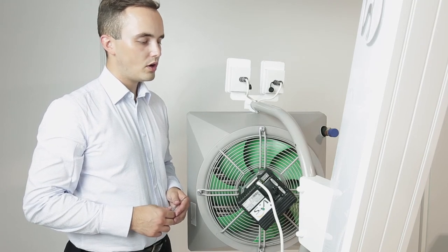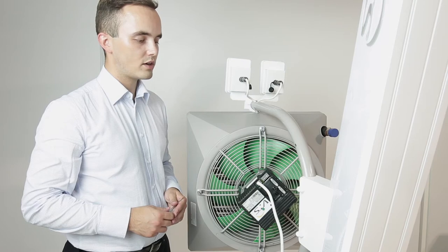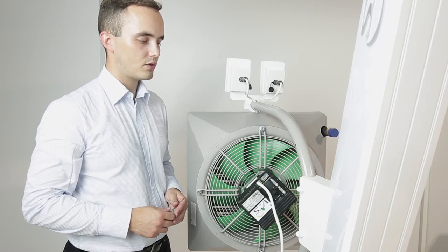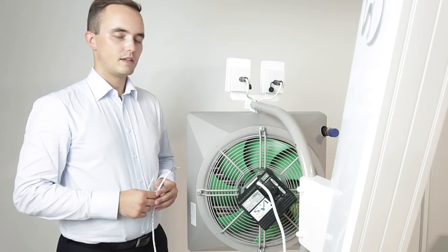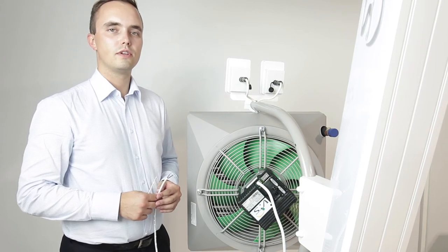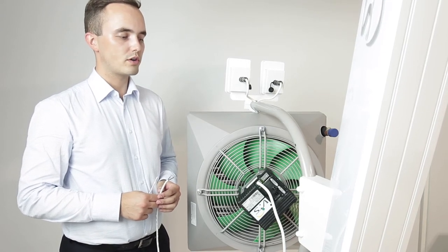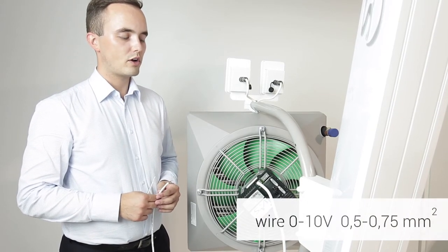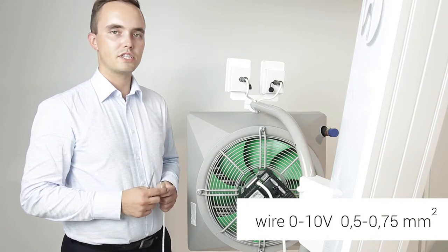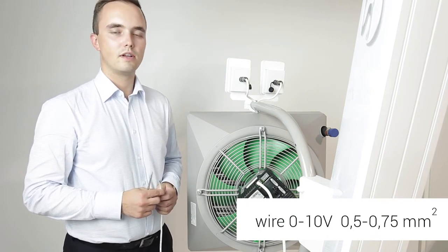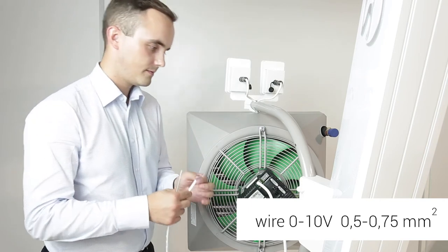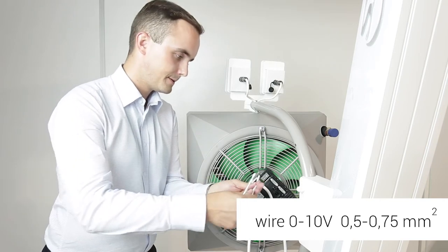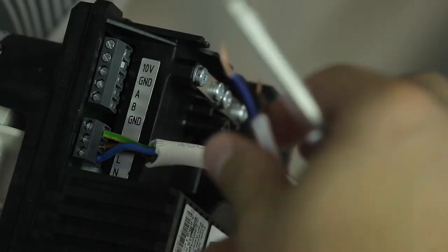Now let's connect a 0-10 volt DC control signal. Control signal 0-10 volt requires cables with a much smaller cross-section. Recommended crossings are 0.5 to 0.75 millimeters squared. Now let's connect and ground the control signal.